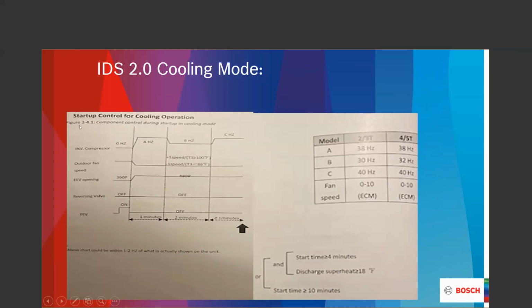So here we are. We started out in that 38 hertz rating. Now we're going to drop to the B hertz rating, which is right around 30 hertz on the 2 and 3 ton, and right around 32 hertz on the 4 and 5 ton. And we're going to run for that particular staging for 2 minutes. And we're looking at here, what did we do last hour? Where can I be the most economical as far as my next staging? Where did we create a satisfaction of the set point on the controller, the thermostat? And so that's the logic behind this particular 2 minute period.